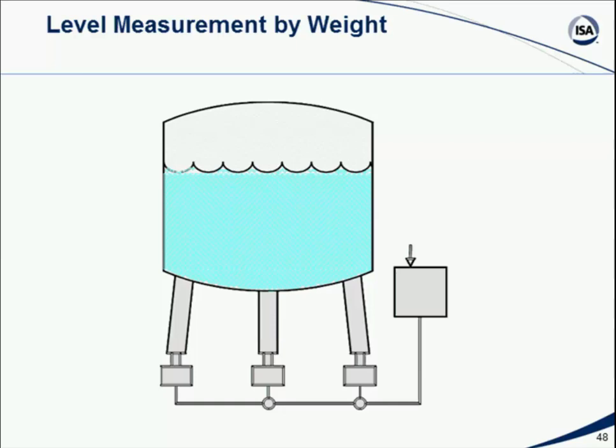Now, again, there are certain issues here. You need to make sure that the tank is very properly balanced. You don't want it to be leaning one way or the other because it has to sit exactly on these load cells. So I've seen applications where you've got a tank and the wind is blowing and pressing against the side of the tank, which actually causes the level indication of the tank to change because the tank is now sort of pushing one way, so it's taking the weight off one of the legs and putting more weight on another leg. So you have to deal with things like that. As I said, the tank has to be absolutely leveled appropriately, but this is a technique that's used in a lot of different applications. So we can make a level measurement inferentially by making a measurement of the pressure or the force pushed downwards by the tank as the fluid level in the tank increases.